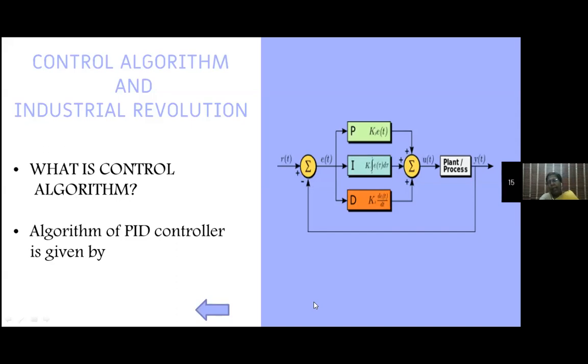In the beginning stages, this PID algorithm was realized using pneumatic components - pneumatic equipment operated using pressure signal as input. For example, the pneumatic amplifier, pneumatic relay, bellow element, diaphragm element, flapper nozzle system - these are some of the pneumatic elements. Using these, the PID structure is realized: the amplifier is constructed using pneumatic elements, along with an integrator and differentiator, combining all three.